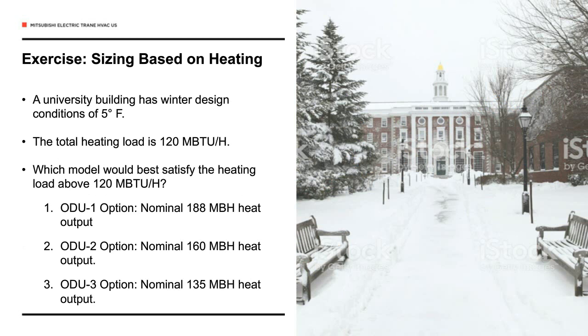If we look at an example, we have a university building that we're designing a VRF system for. Its winter design temperature is 5 degrees Fahrenheit. And our total heating load for this system is 120 MBH. So which model of the following ones shown would satisfy the heating load of 120 MBH? Outdoor unit 1 option, we get a nominal heating output of 188 MBH. Outdoor unit number 2 option, we get a nominal heating output of 160 MBH. And outdoor unit number 3 option, we get a nominal heating output of 135 MBH. Now bear in mind, nominal heating output is at 47 degrees ambient, 47 above zero. So we want to make sure that we have the heating capacity we need at 5 degrees.